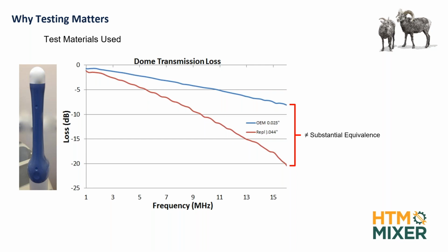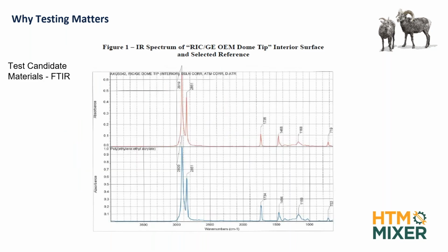So, and again, you can reverse engineer these things. You don't have to guess, and the OEM is not going to tell you what it is, but we have tools available to us that we use, and a lot of folks do. And ours is Fourier transform infrared spectrometry, where we can put a probe that hooks up to the device on the material itself, and it'll show us what that spectrum looks like. And then it'll not only show what it looks like, they have a huge library of what those spectrums look like from the maker of the device, and it'll tell you exactly what it is.